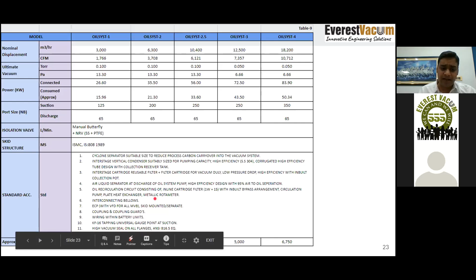We have very controlled power consumption, saving almost 15 to 20% of connected power on average. The systems are compact and come with all standard accessories needed to run efficiently — the cyclone separator, interstage condensers, interstage cartridge reusable filters, air liquid separator, oil circulation circuit, piping, bellows, ECP, coupling guards, and everything. It's a fit, plug and play unit — you just give us the process connection and electrical wiring, and we can run the machine immediately on site.